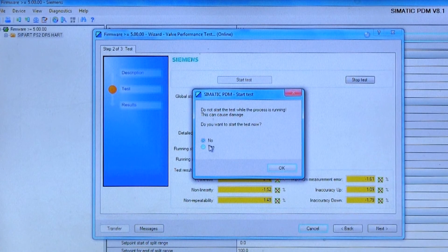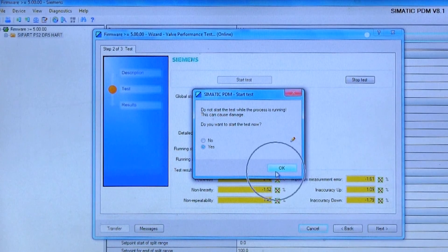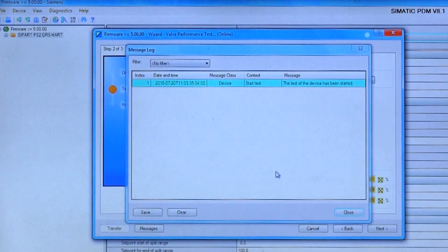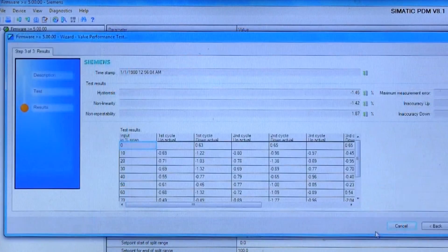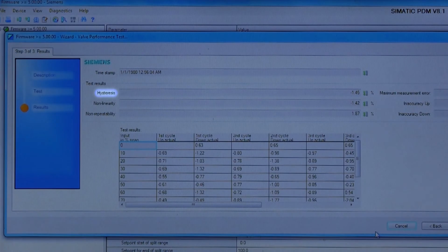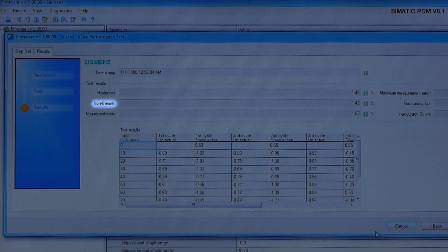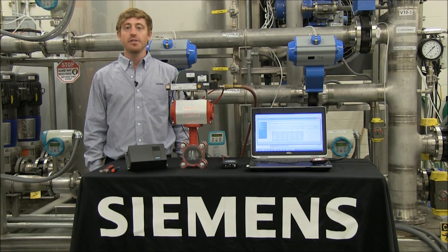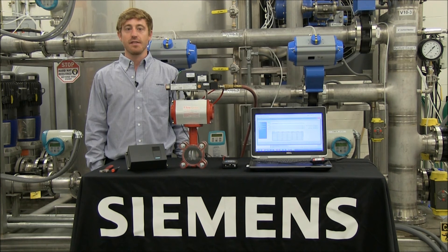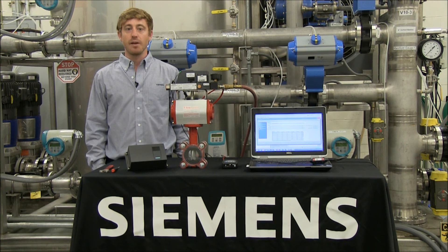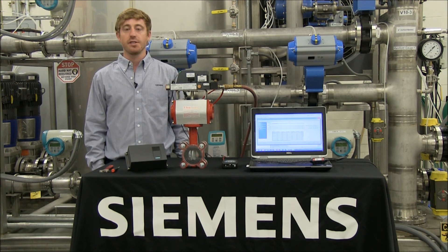The valve performance test will automatically run three cycles and record the data points. Once the test completes, you'll have the following results: hysteresis, non-linearity, and non-repeatability. You can use these data points as a baseline to assess the current status of the valve, as well as a comparison to see how your valve performance has changed over time.